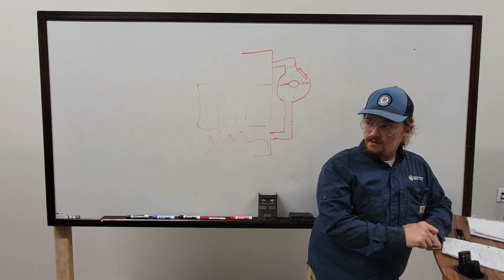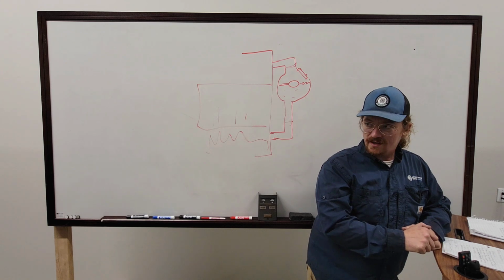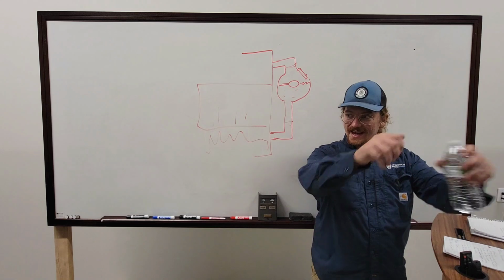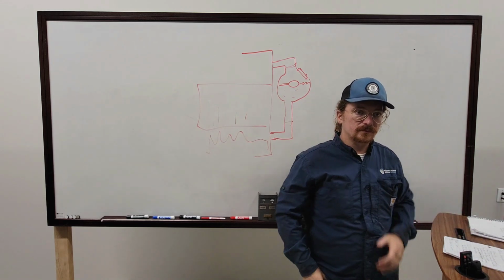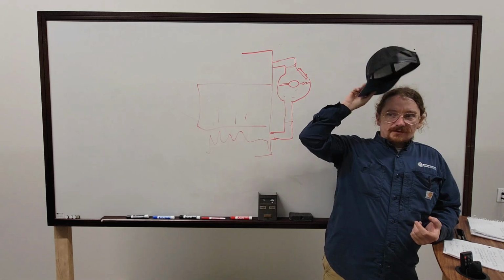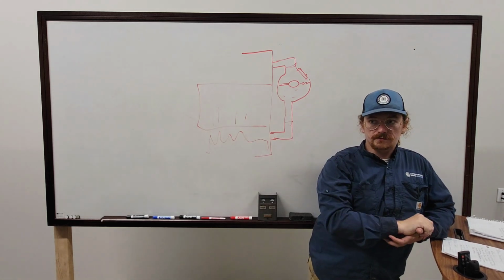No, because I was just staring at this thing, and the low fire side is set at like 200, and the high fire is set at like 185. So it's like, why is the high side set low and the low side set high? And now I know. It's working reverse theory, trying to heat, so everything's getting cold. I was thinking your high temperature should be your high number and your low temperature should be your low number, but no, it's calling for a stage at a low. Yeah, it makes sense now.